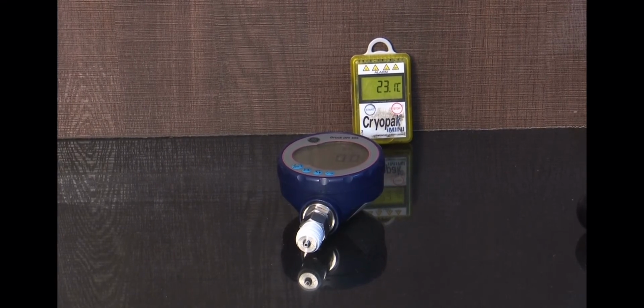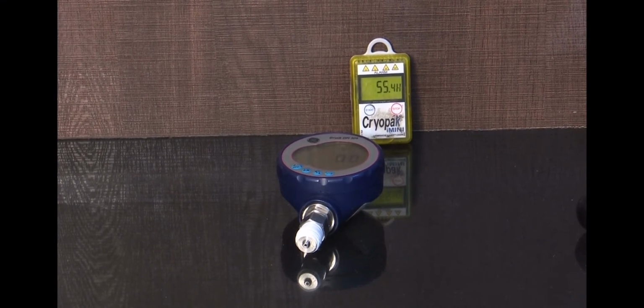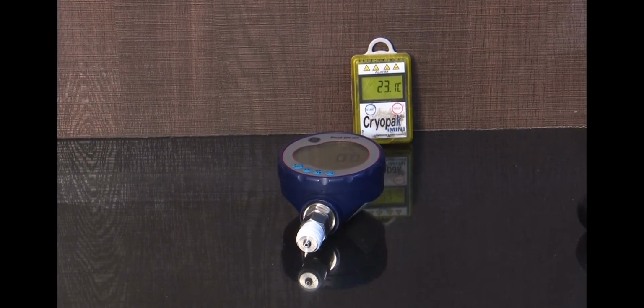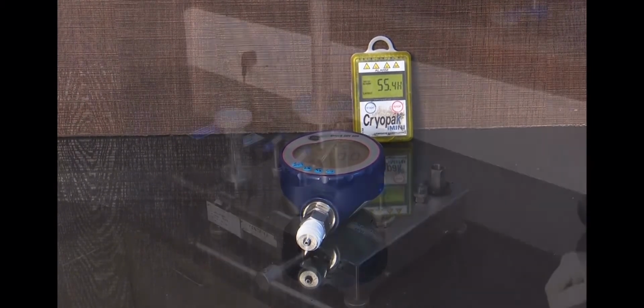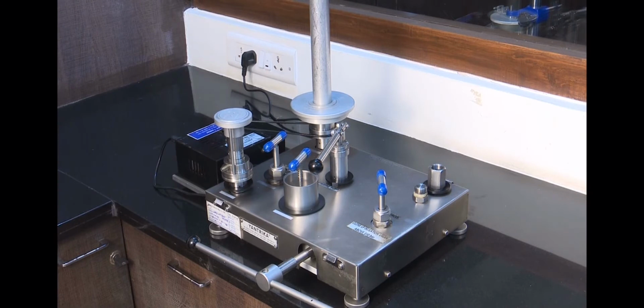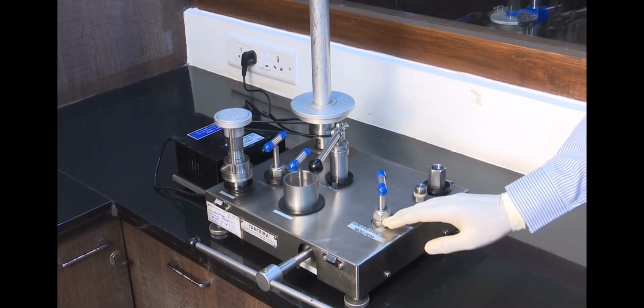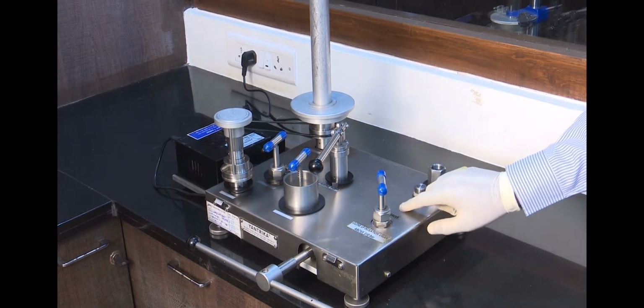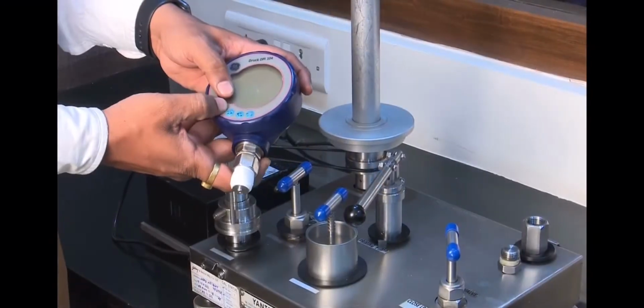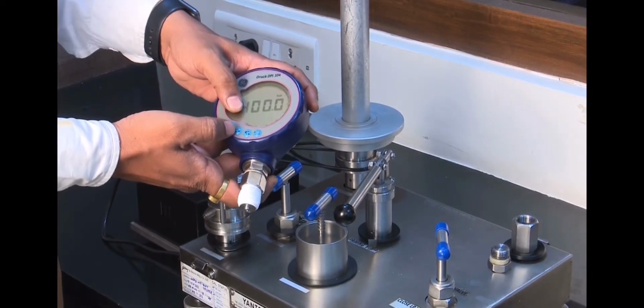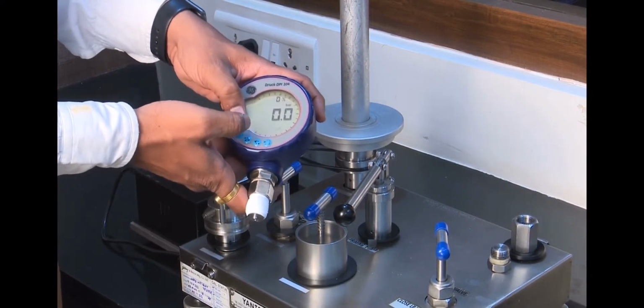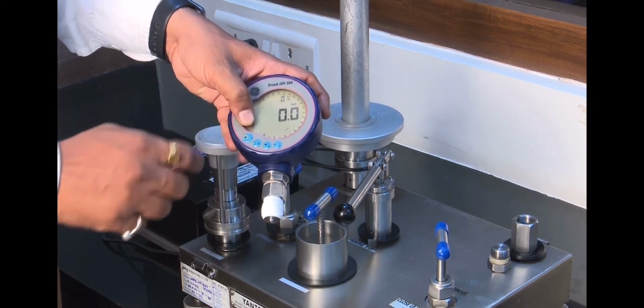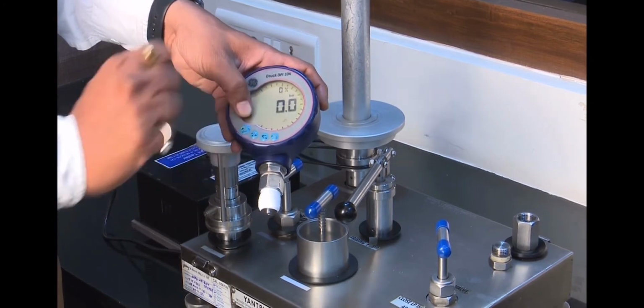Before starting calibration, ensure that the environment condition is maintained. The temperature should be between 23 plus minus 1.5 degrees centigrade and humidity should be 40 to 60% RH. For calibration, we will use dead weight tester. This is called pressure connector and this is dial of the pressure gauge. This pressure gauge is having range 0 to 400 bar and 0.1 bar resolution.